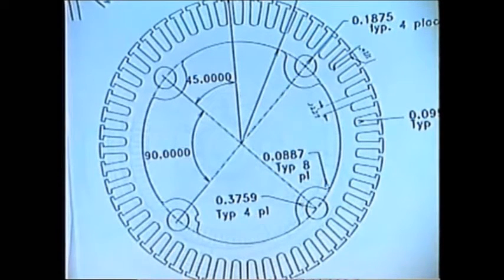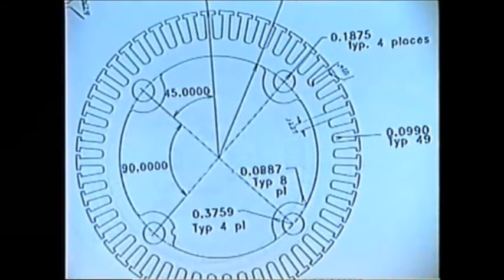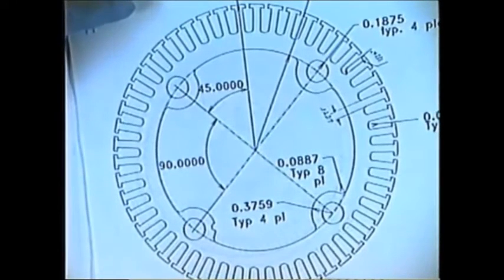There are a couple of innovations in this, and the next one will be more efficient. The 50 horsepower design is built for very simple construction. If I want a 100 horse, I take the same stator wound left hand and it goes in the same motor. All parts are universally designed so I can have a 50, a 100, or go to a 200 using the same stator plate. I can wind this to get 10 horsepower, or make it super efficient at a horse and a half using the same size frame.